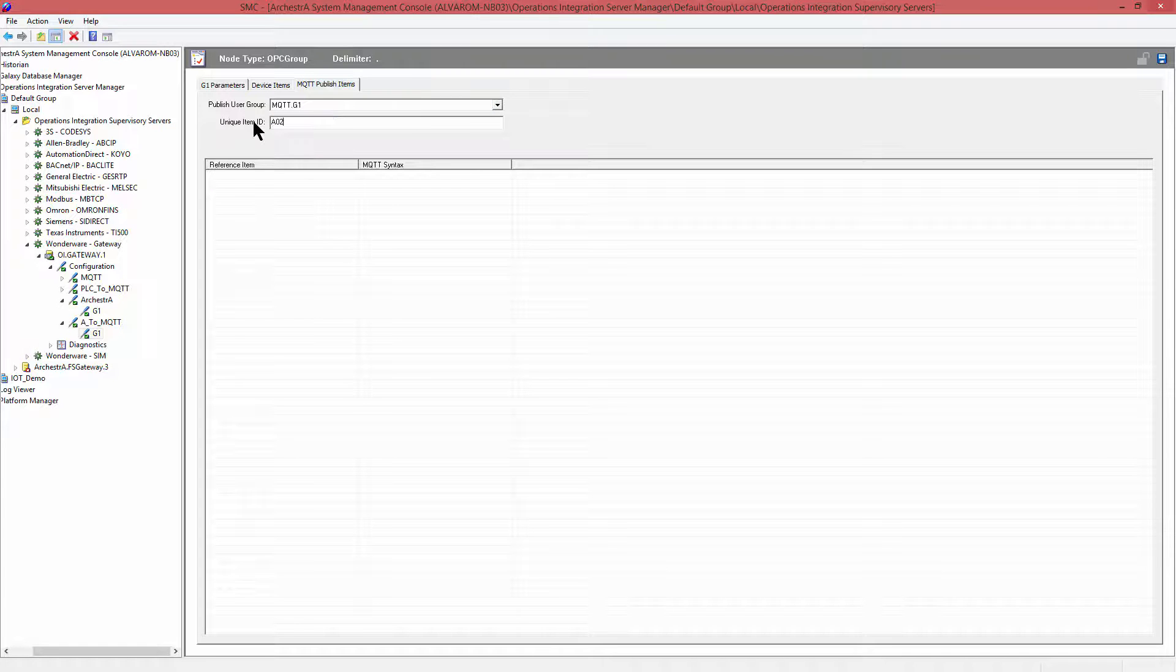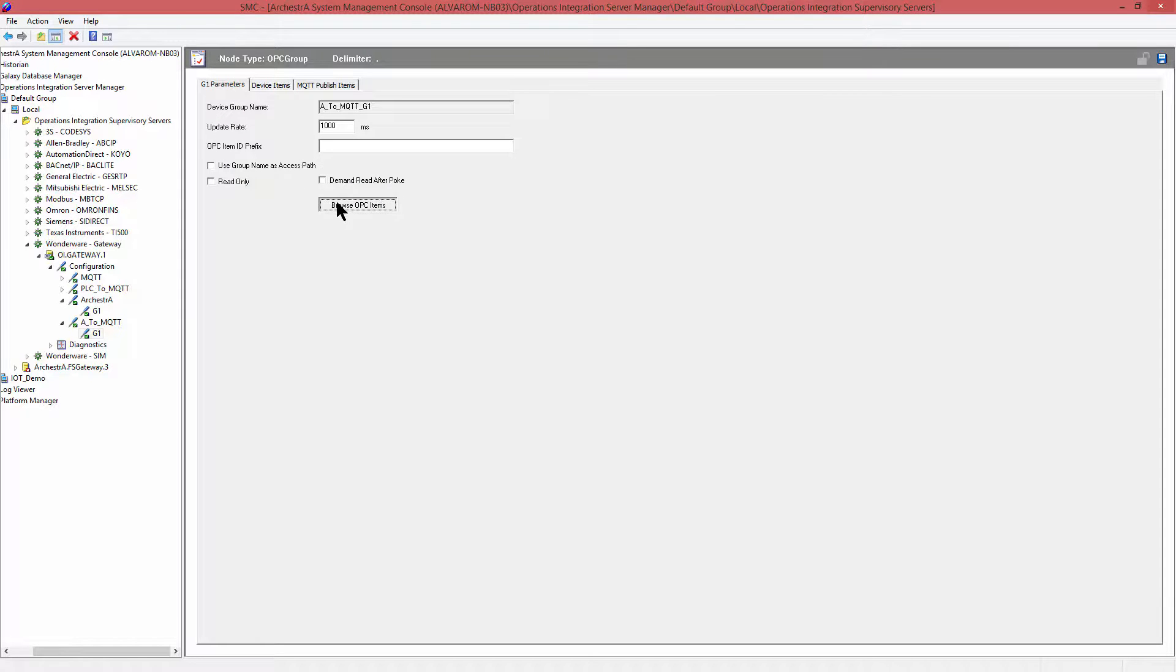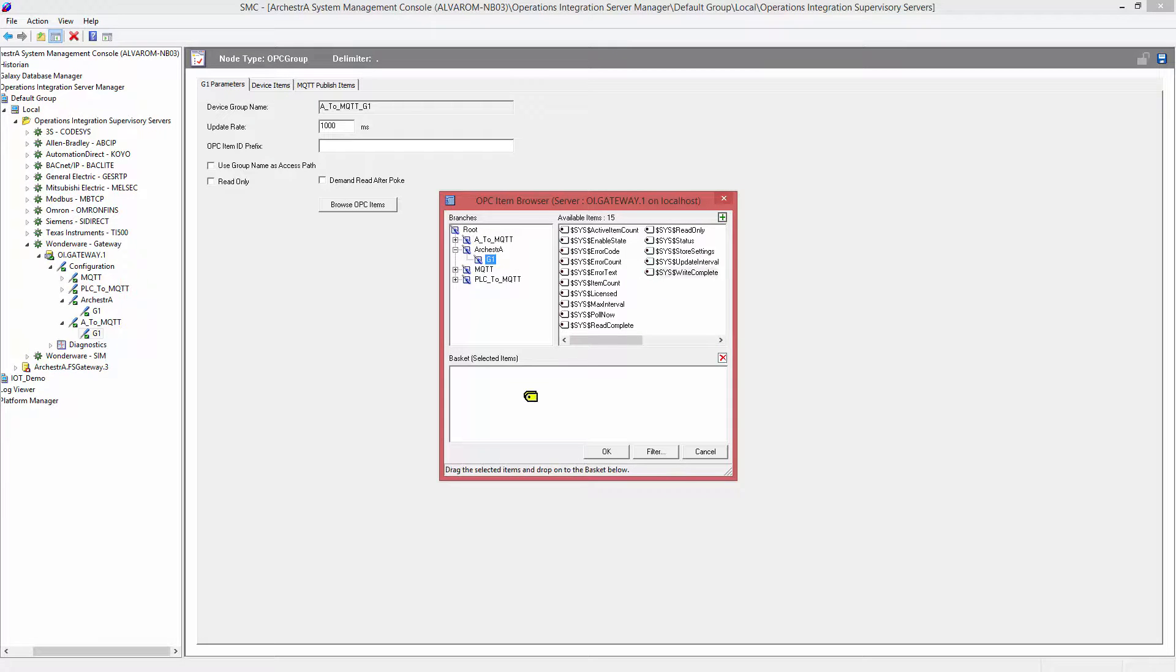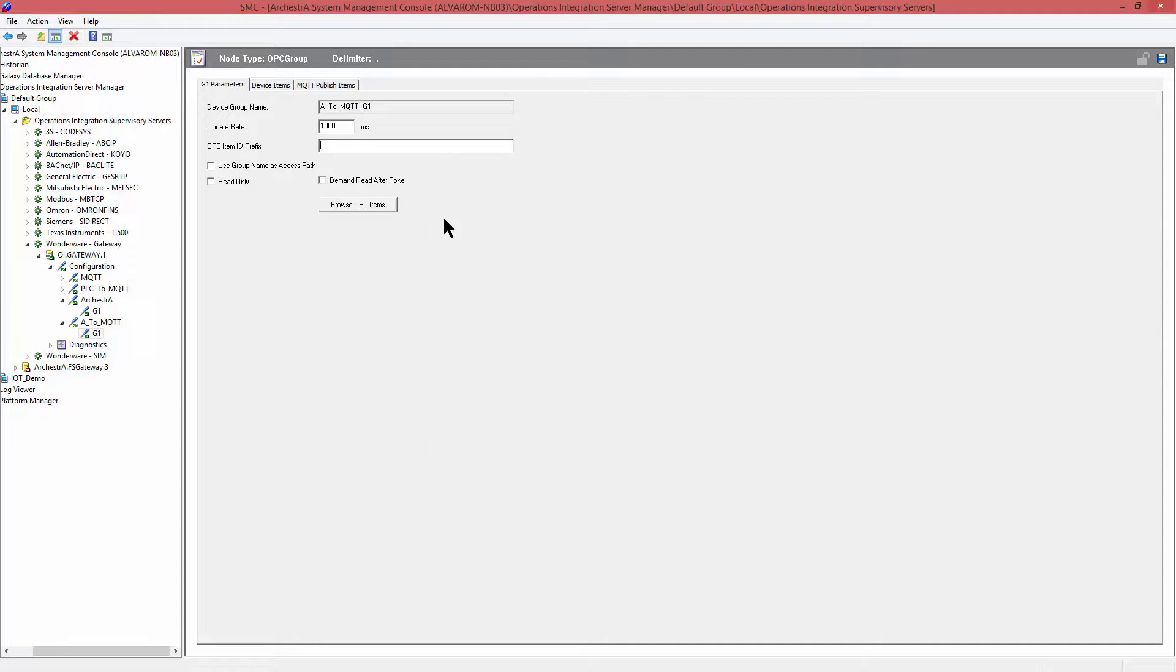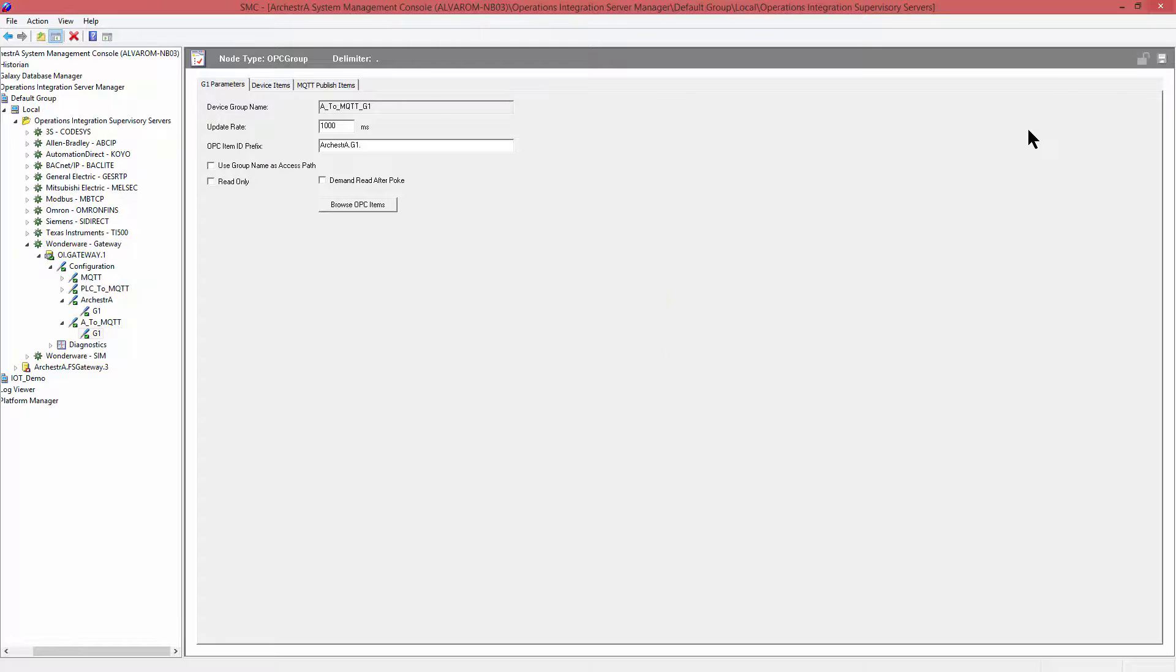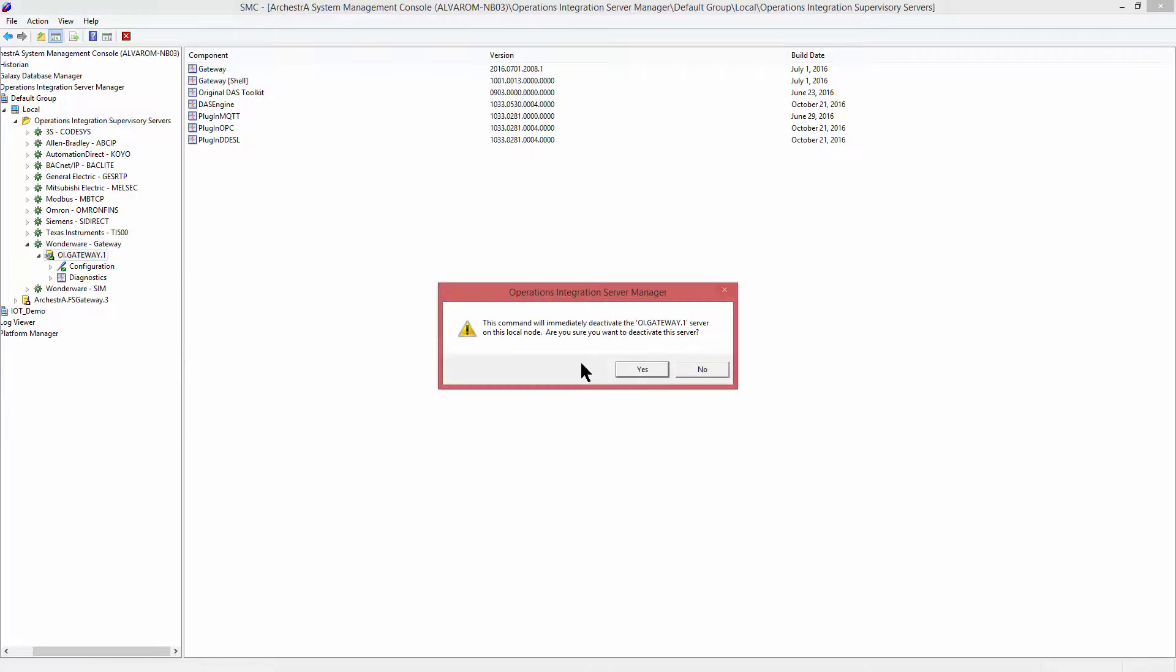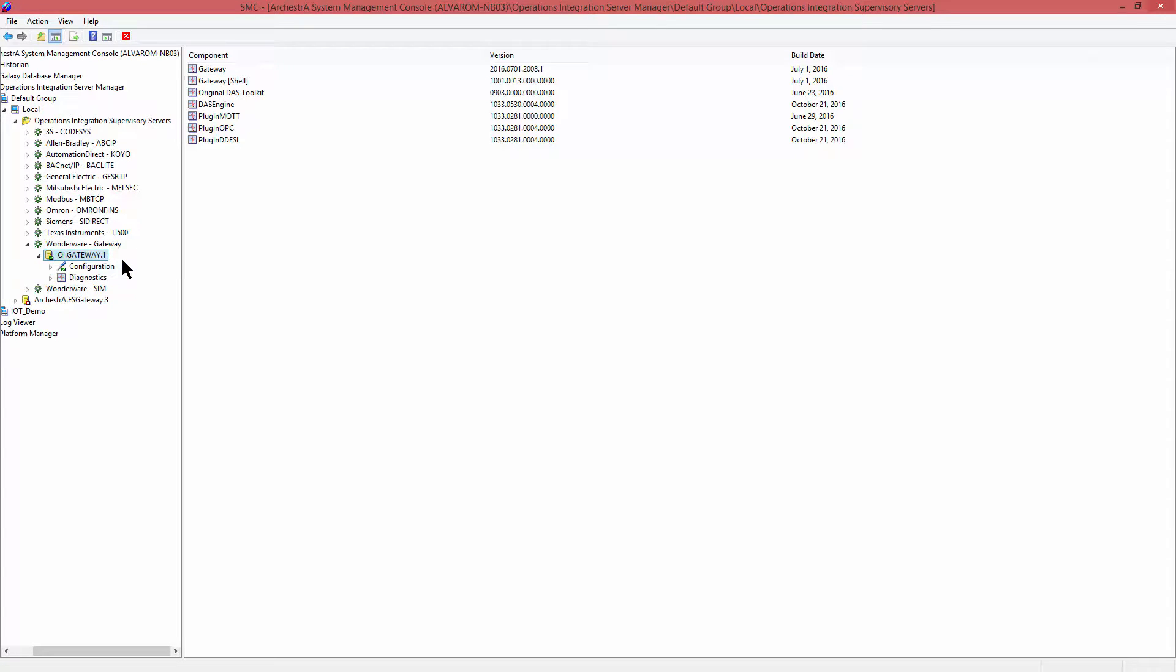We create the uniqueness ID, but now we also want to remember, add that OPC prefix that is important to keep the syntax simple. I show here how to use the OPC browser, in case you don't remember how to utilize that OPC syntax. Instead we use the OPC browser to help us. So that part is now configured. The next step is to deactivate and reactivate the OI Gateway to consume the changes that we did for the ArchestrA connection.